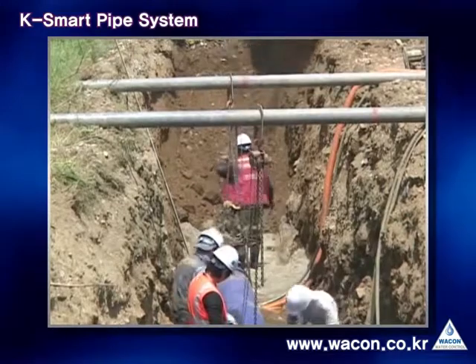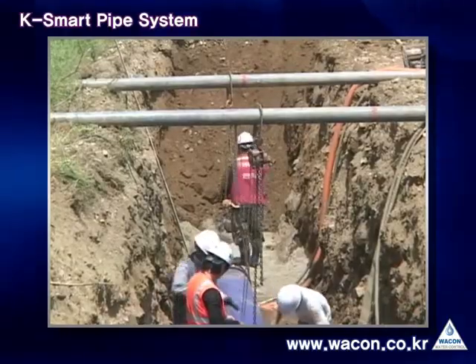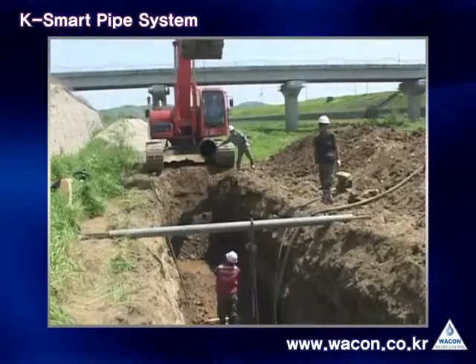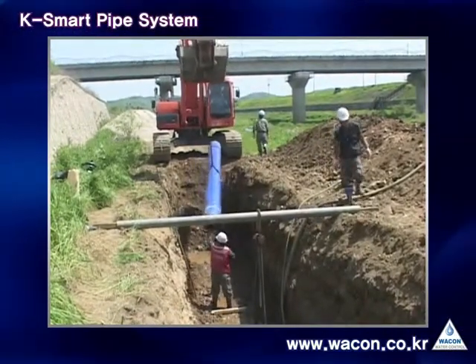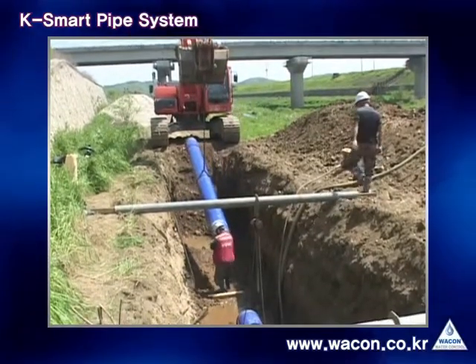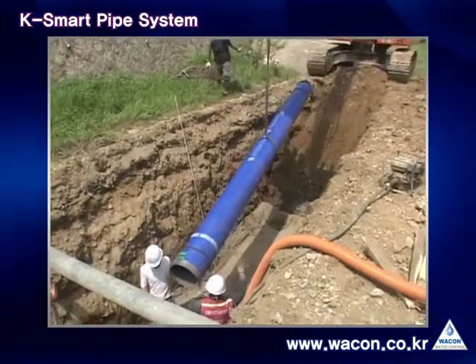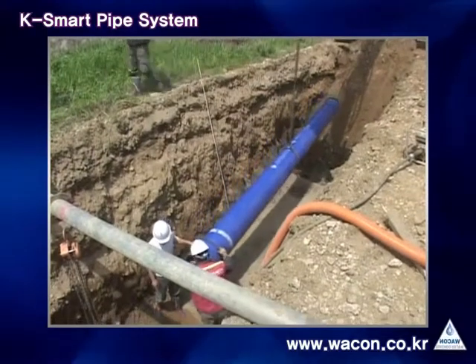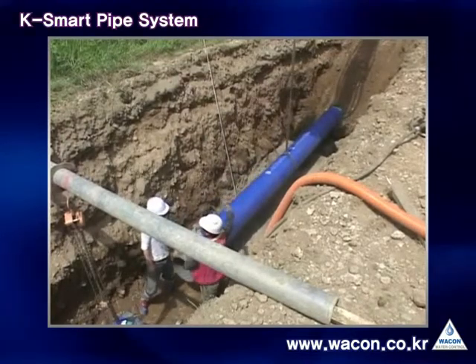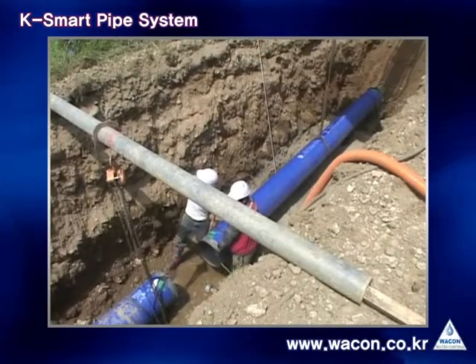In this progress, we will dig the ground. It is very good to make the workspace big enough — approximately two pipe lengths along the layout path in advance. This step is transporting pipes. After digging the ground, when transporting pipes, you have to bind the pipe with a rope. This method is the best way to transport pipes to the construction location without damage. There is also another way to mount hooks on the ends of pipes, but you must handle carefully not to scratch the coating. If damage occurs, you have to repair the damaged coating at the actual field.